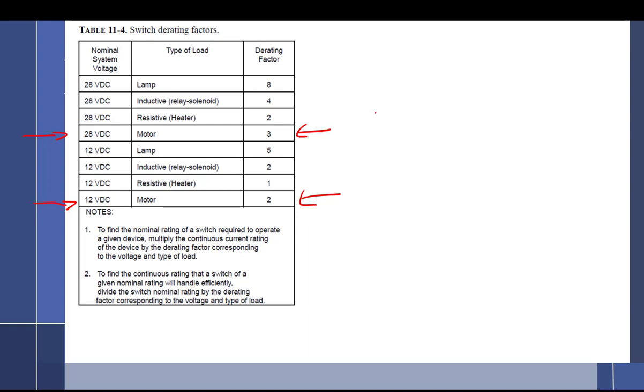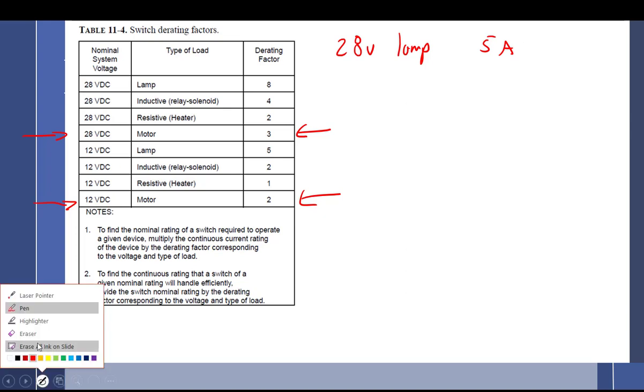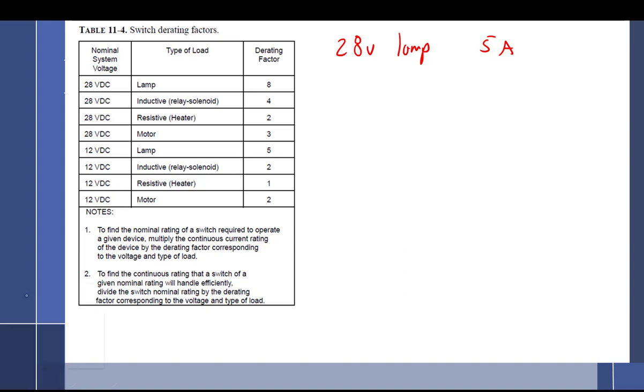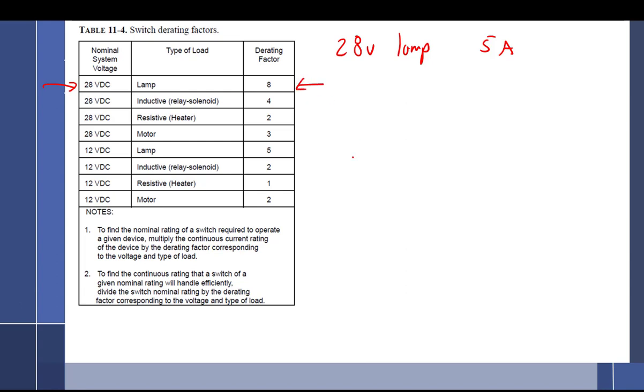So I'm derated by a factor of 3 for 28 volt and factor of 2. Example: I have a 28 volt lamp that draws 5 amps. So what am I going to look for here? 28 volt lamp - I got a derating factor of 8. So basically I just multiply that times 8, and I come up with 40. So I should be looking for a 40 amp switch.